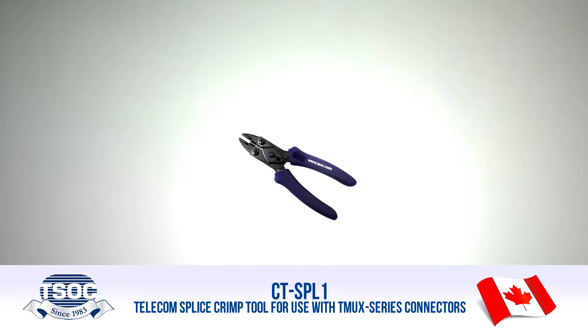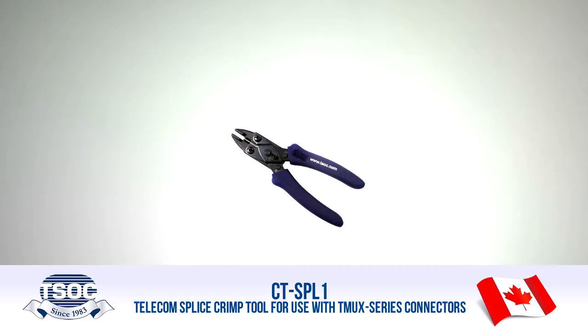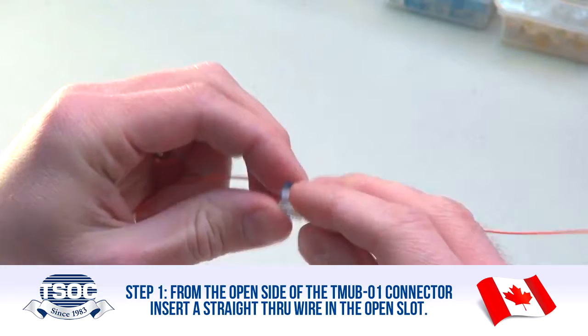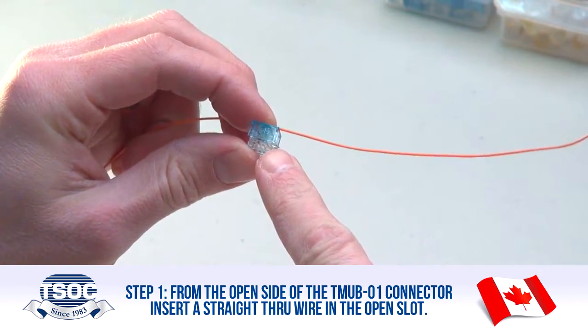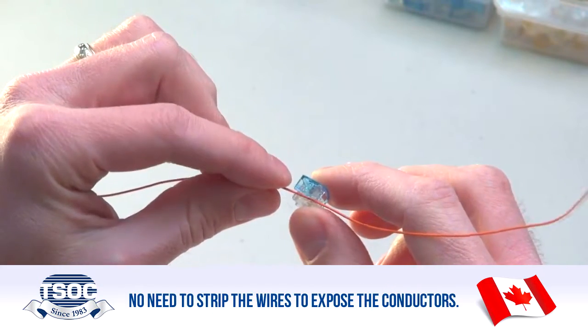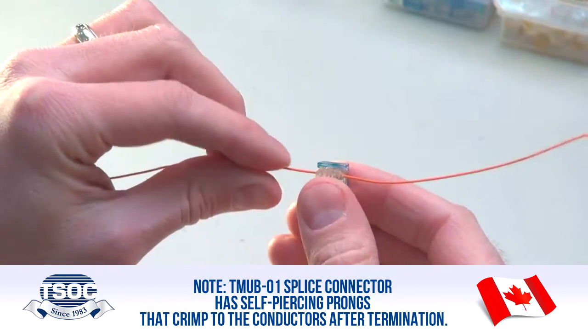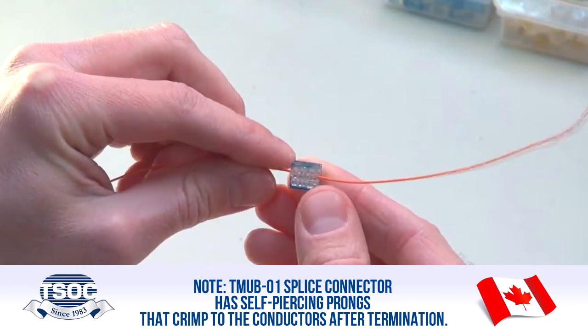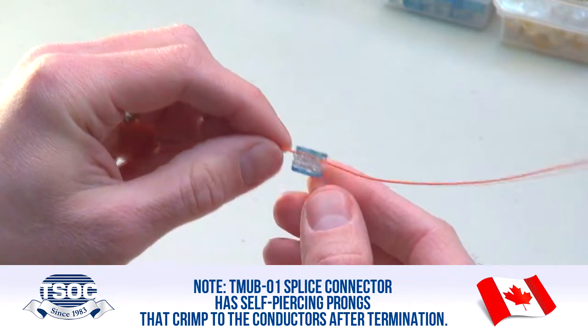CT-SPL-1 Telecom splice crimp tool for use with TMUX-series connectors. Step 1: From the open side of the TMUB-01 connector, insert a straight-through wire in the open slot. No need to strip the wires to expose the conductors. The TMUB-01 splice connector has self-piercing prongs that crimp to the conductors after termination.